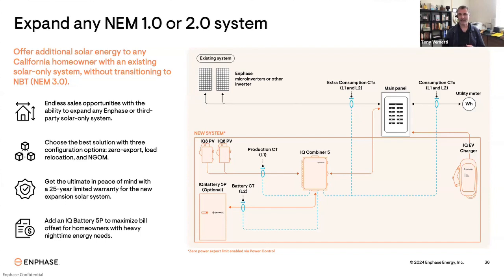Now, the challenge for those customers is that if they want to increase capacity on their system, they want to add more solar panels, they're limited only to 1 kilowatt, just a couple of solar panels, or else they're going to be shifted over to the net billing tariff. That's obviously not what those homeowners want. So we have a way, and these are approved configurations by the utilities in California, to install an additional system with Enphase components that can help provide more solar power, and it's configured in such a way that the expansion system, the new system, is monitoring the actual consumption of the home and is allowed to produce as much power as the home is consuming. The expansion system doesn't have the ability, or the permission, to export energy back to the utility grid.